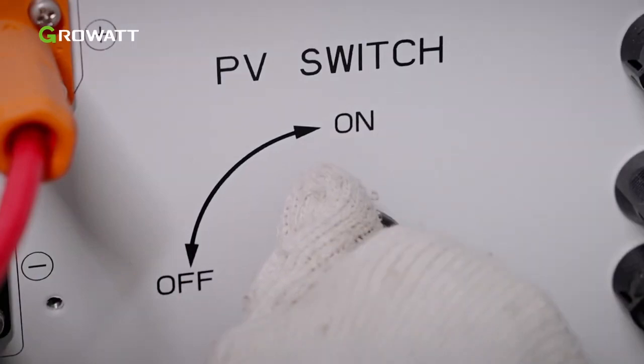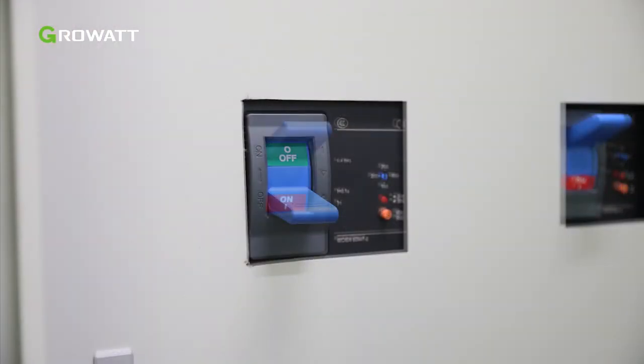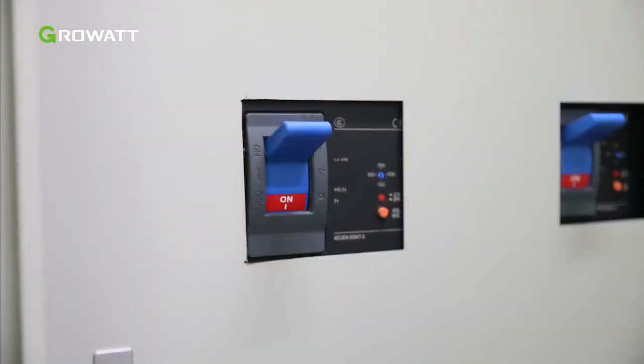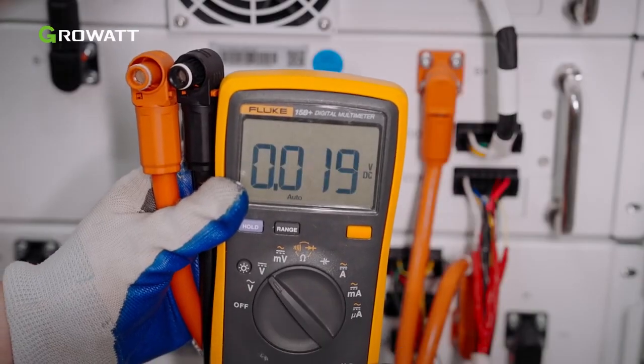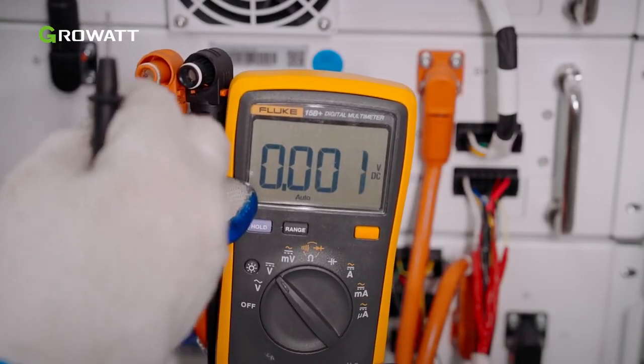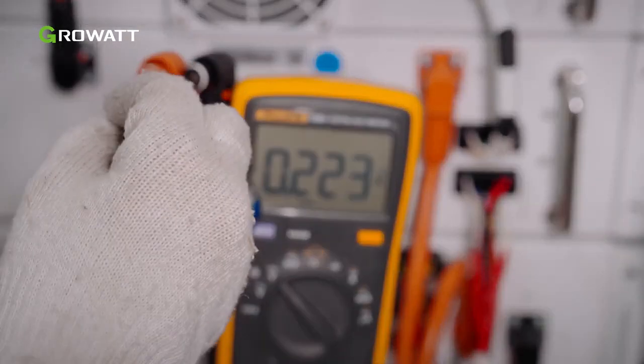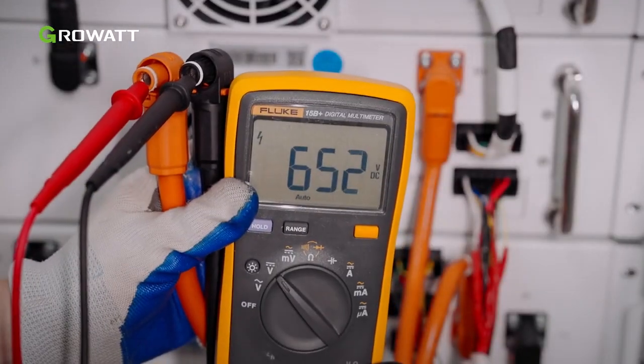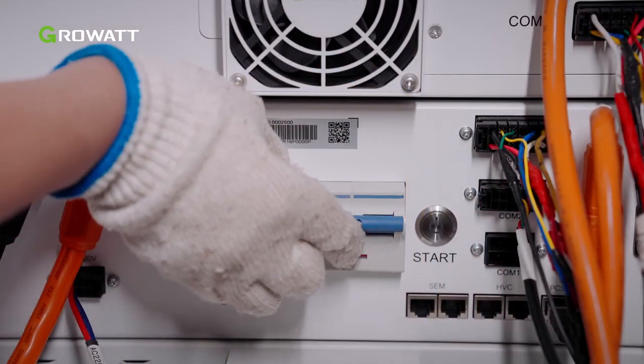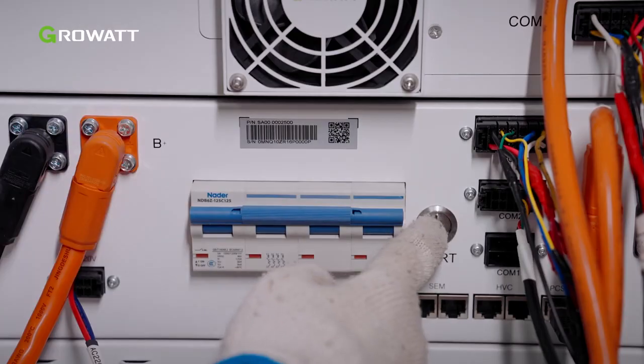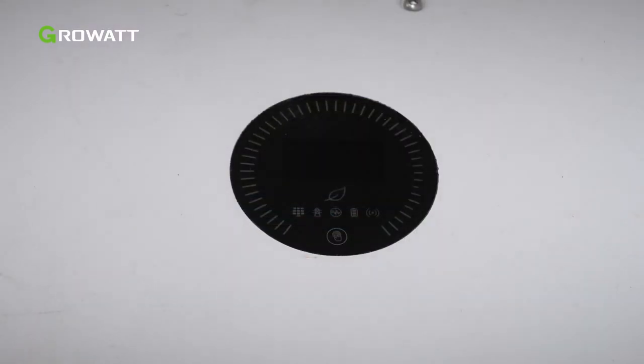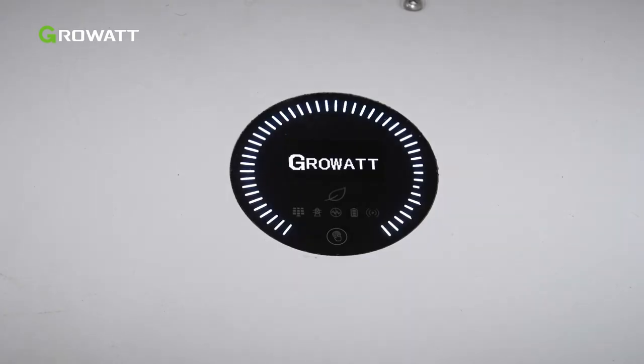Then turn on the DC switches. Turn on the breaker between the grid and the inverter. Test the voltage between BAT positive and BAT negative with a multimeter. Turn on the HVC's DC switch. After completing the above steps, the system will be powered on automatically when all the requirements are met.